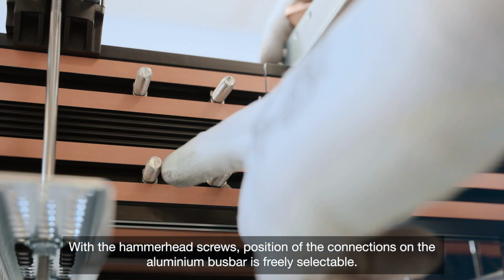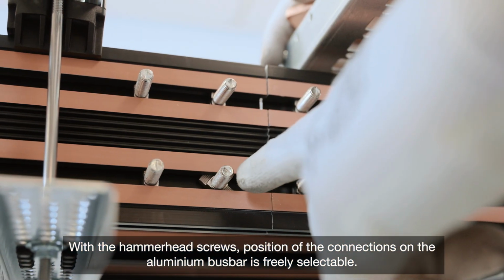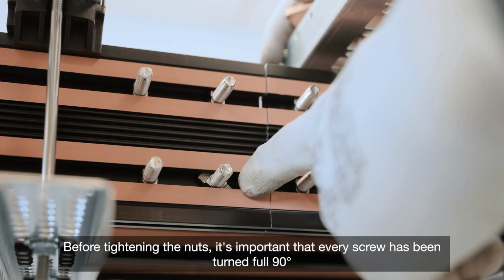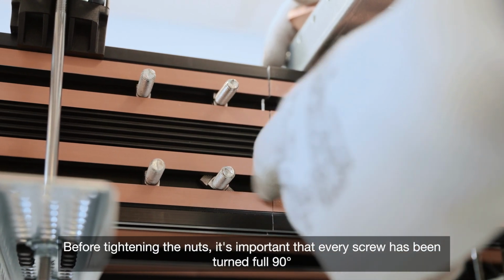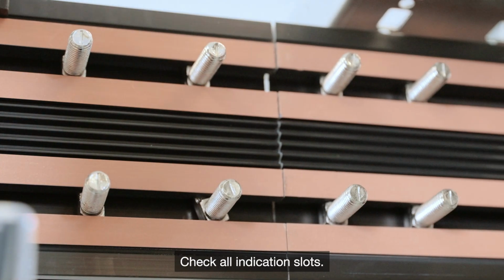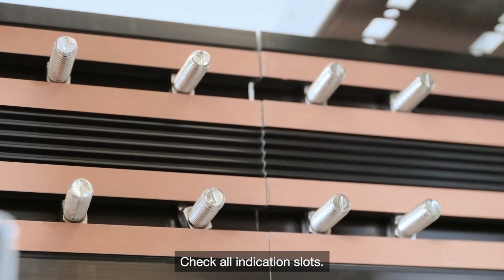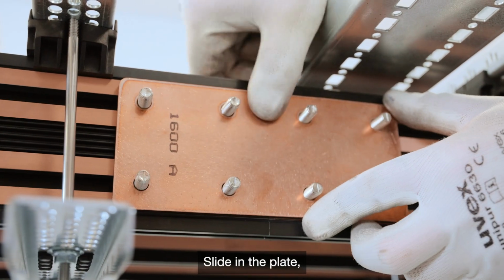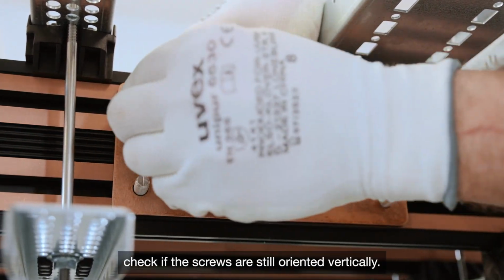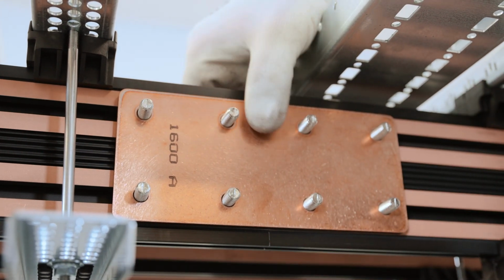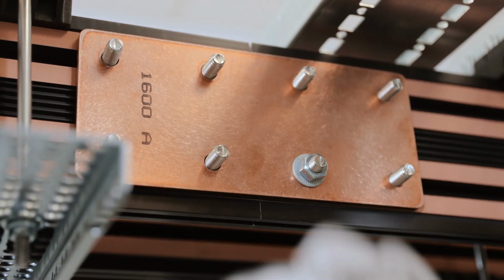With the hammerhead screws, the position of the connections on the aluminium busbar is freely selectable. Before tightening the nuts, it's important that every screw has been turned a full 90 degrees. Check all indication slots. Slide in the plate. Check if the screws are still oriented vertically.